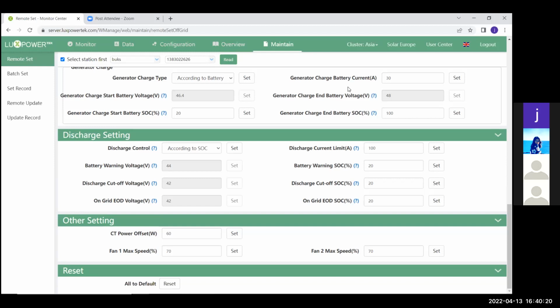Try to use your generator not more than 50% of its capacity to do work on the inverter. That means you have a generator that is not overloaded, and it will still provide a constant and stable source of electricity to my inverters.